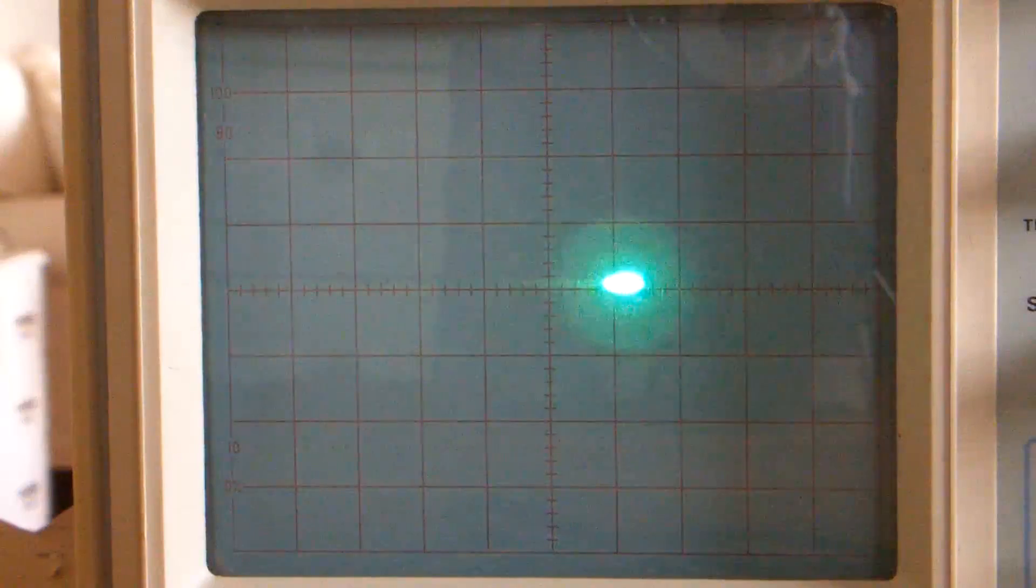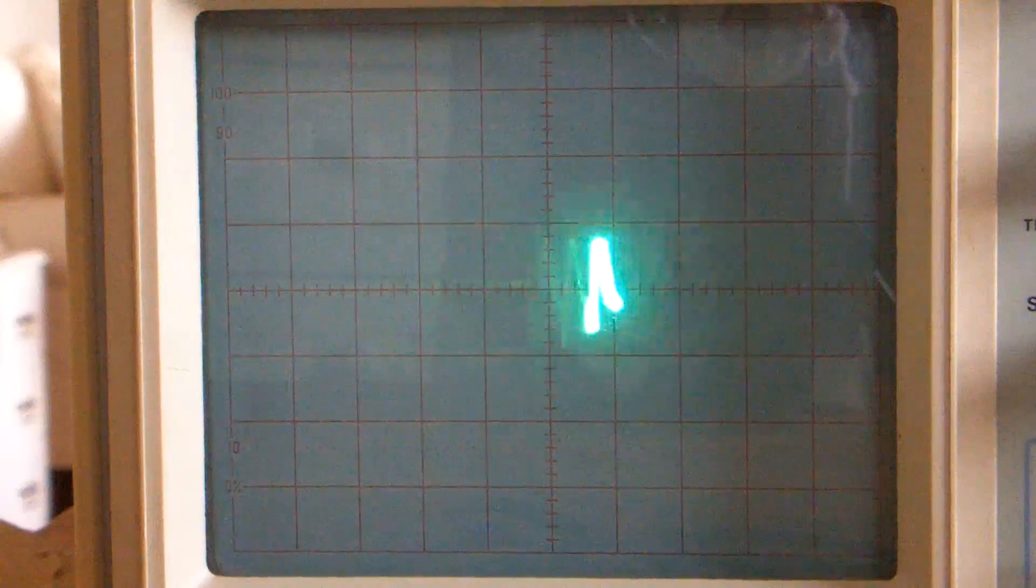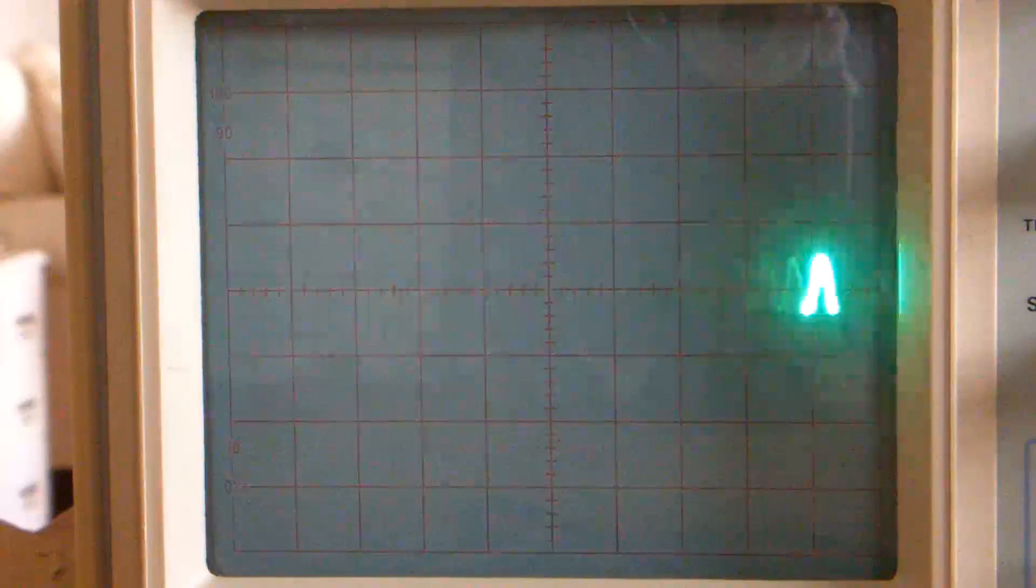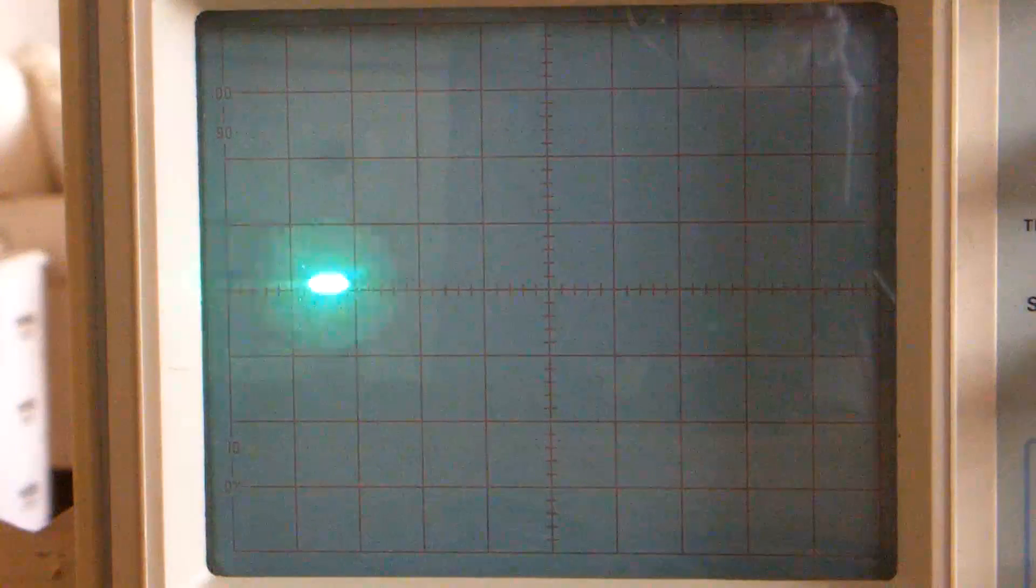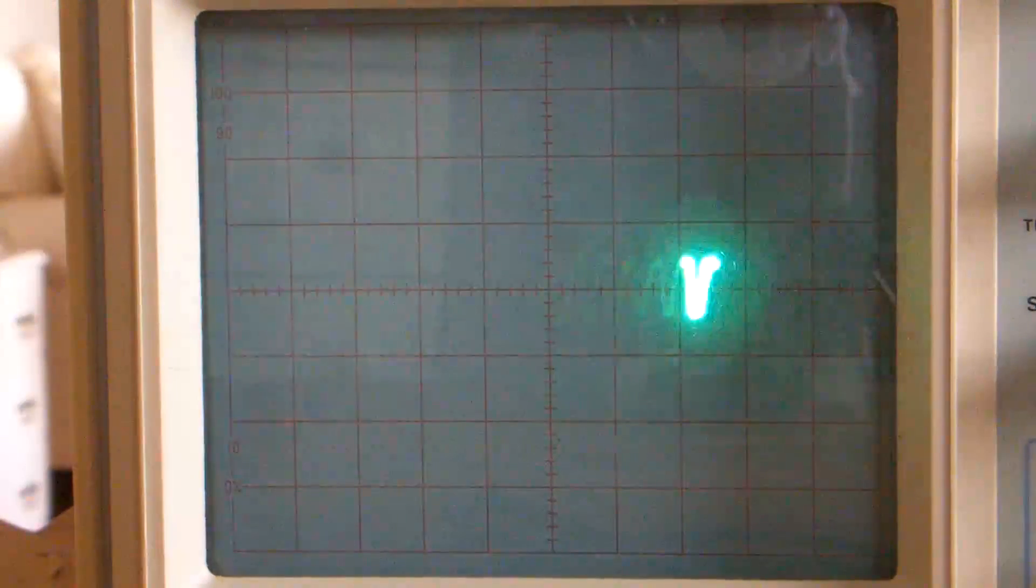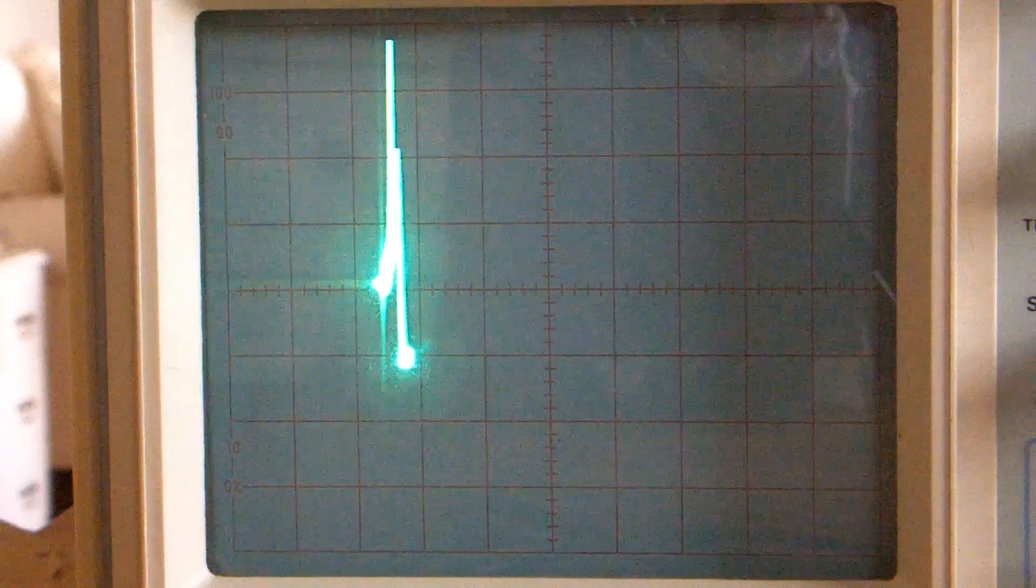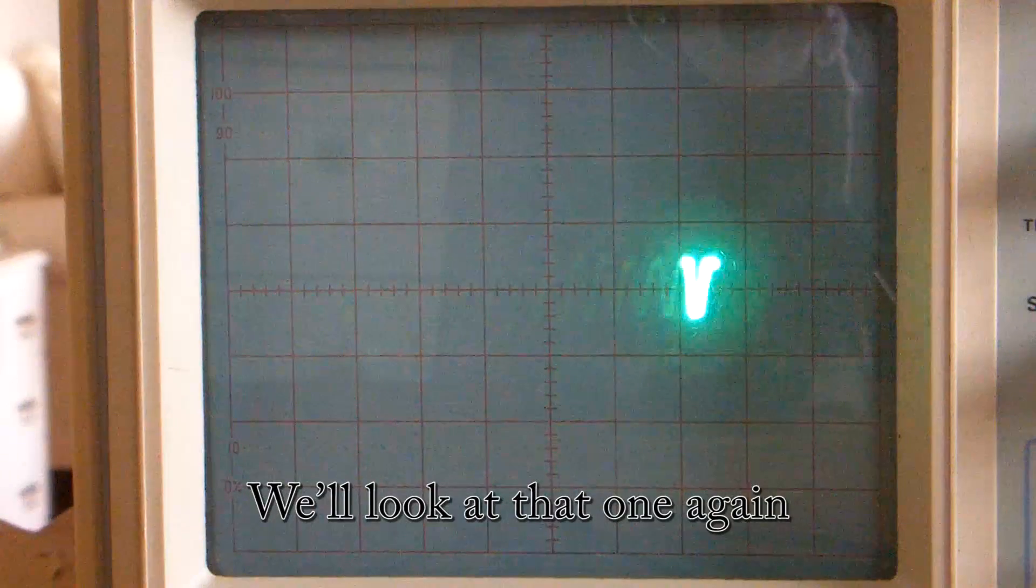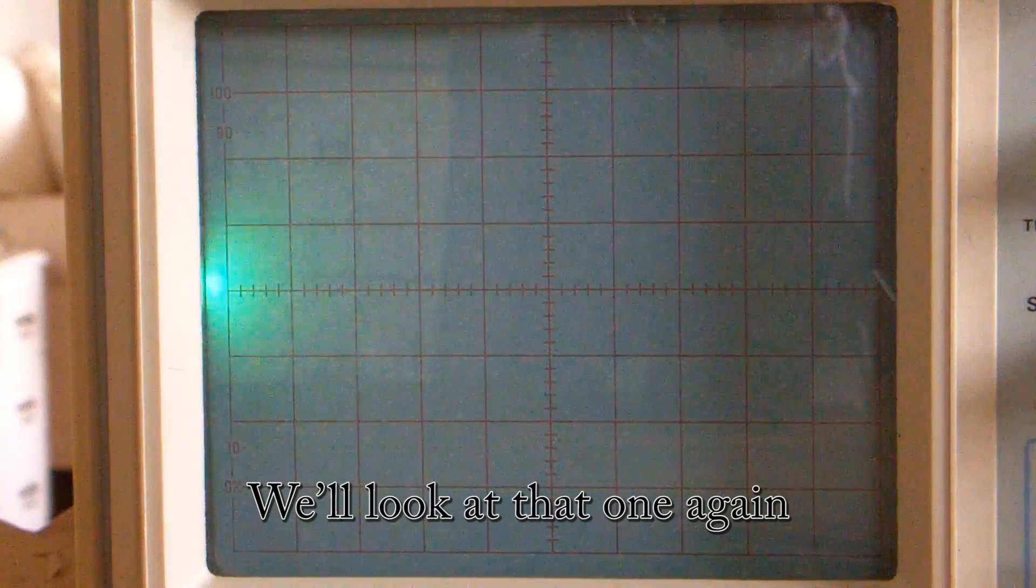In the core, that is how we left it. Think of it as the core being charged either negative or positive. If we switch on to charge in a positive fashion when it was previously left in a negative state, then there's a larger inrush current.